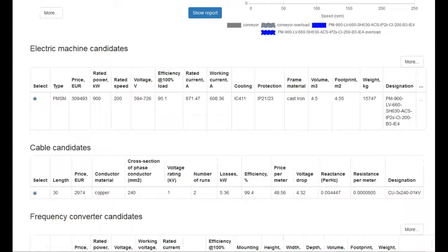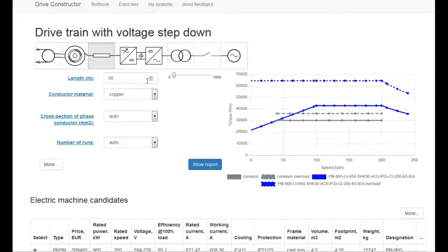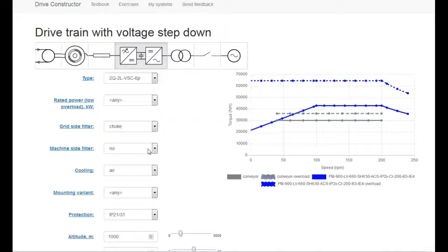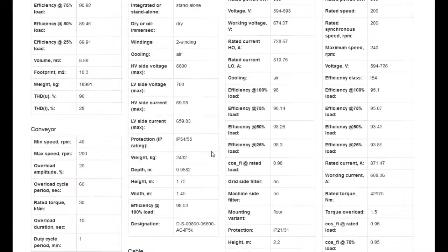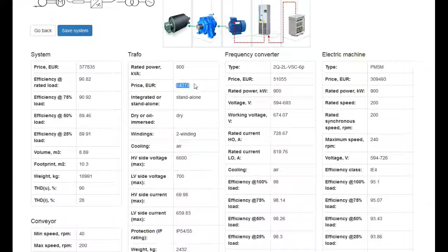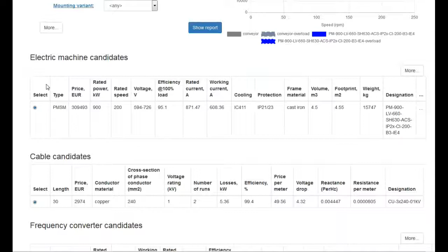We now have a short cable because we take the closest powerhouse with 6 kV, and we see that the efficiency of the cable is quite high, so just very low losses. What can we check here? We go into the frequency converter and look through the parameters. We can play with cooling, of course, but we do not need any filter between the frequency converter and the electric motor. So we reduce the price by that. We look here, it is just 377, even though we have a transformer as part of the system, but we saved quite a lot on the cable and the filter.